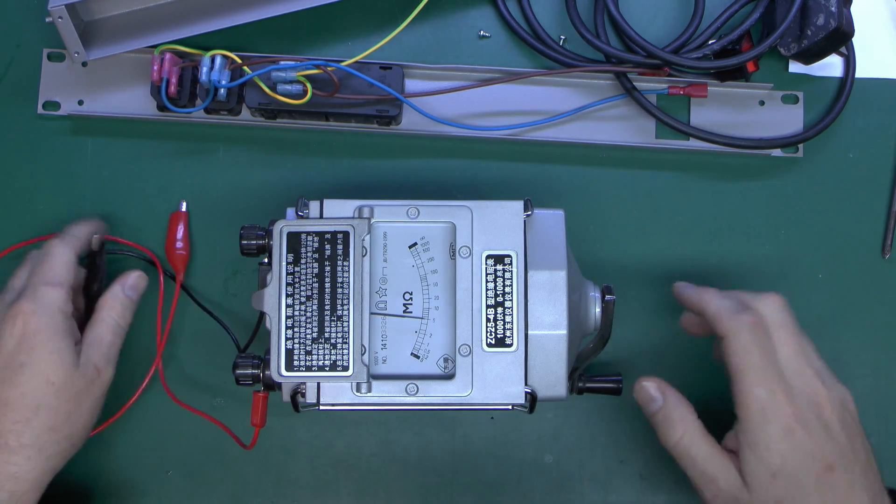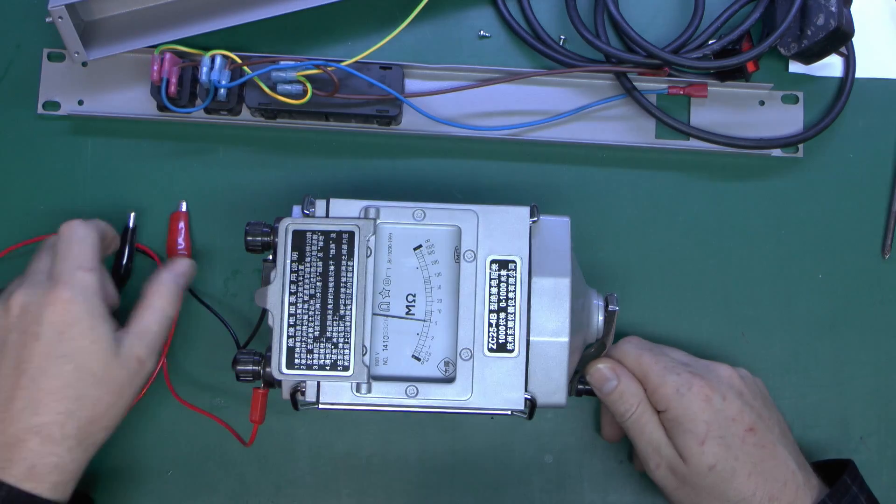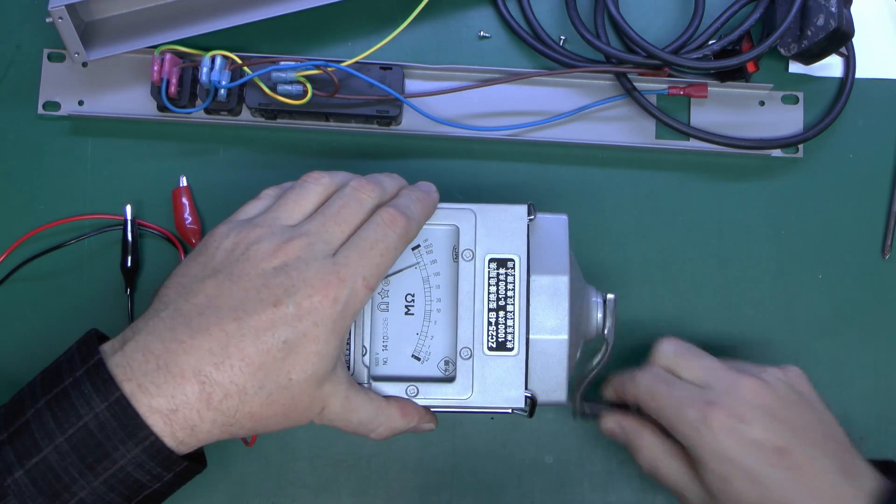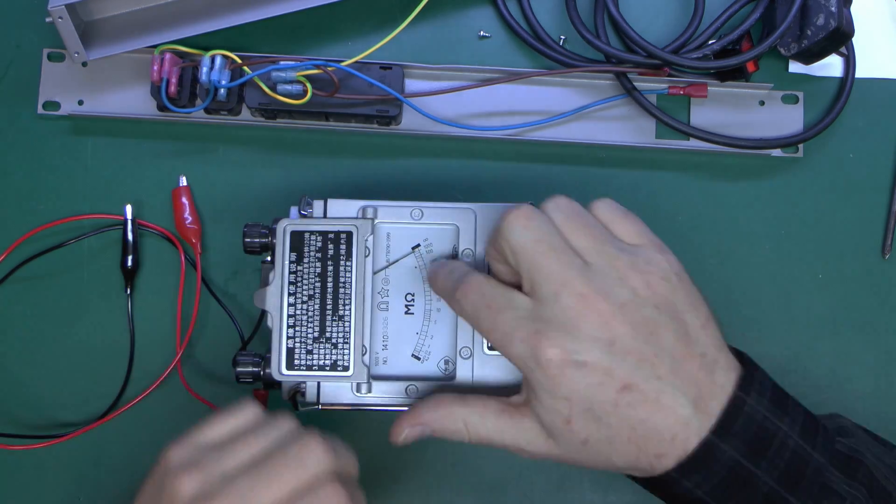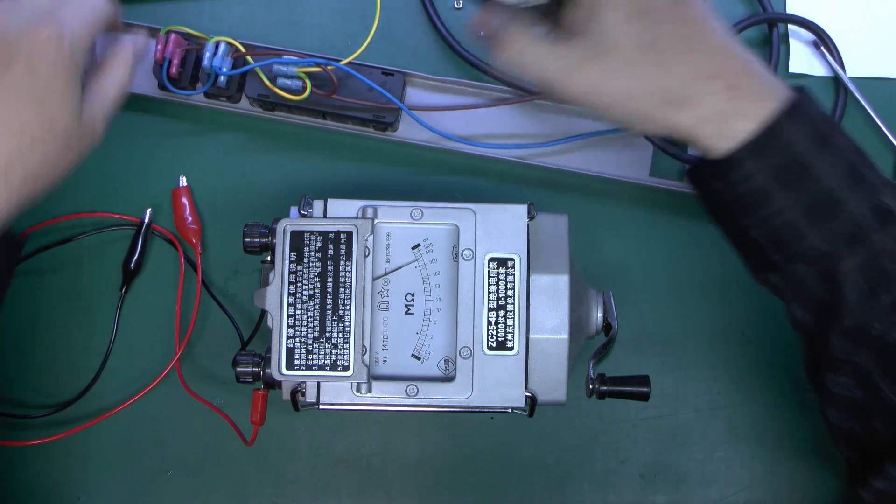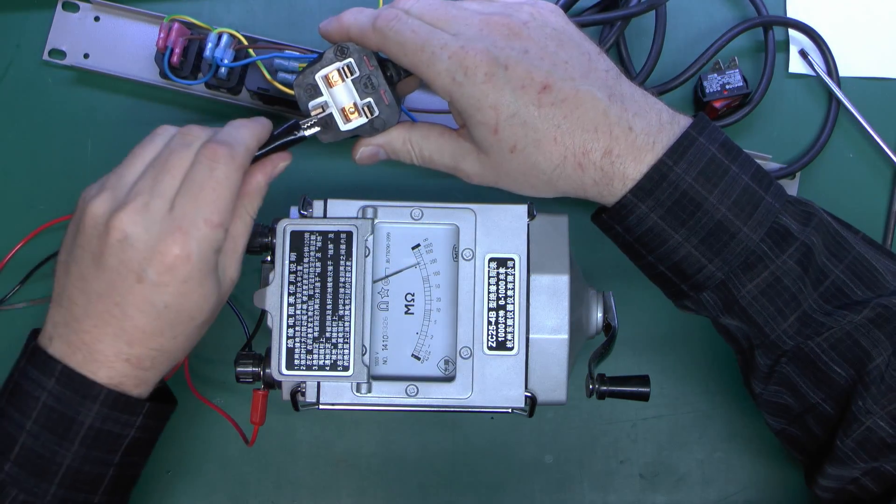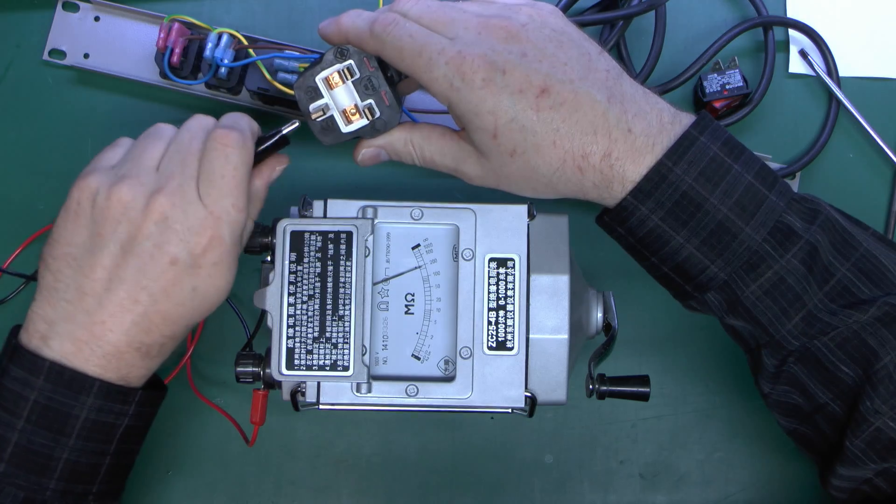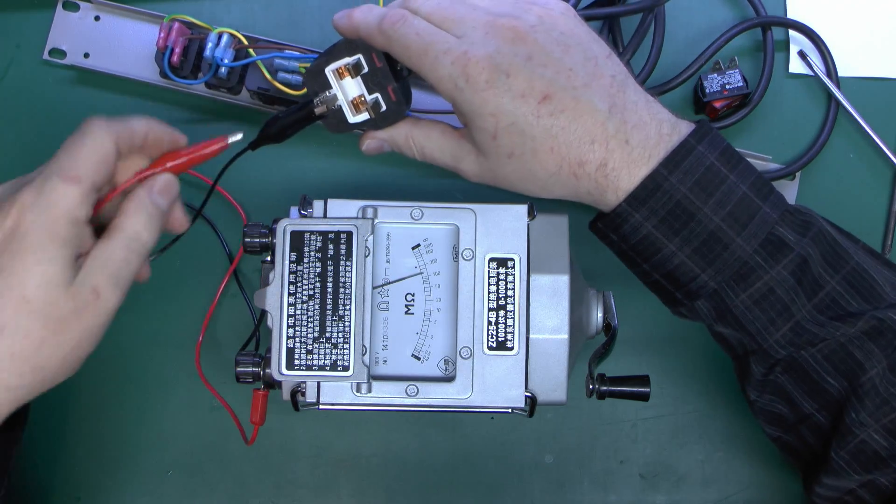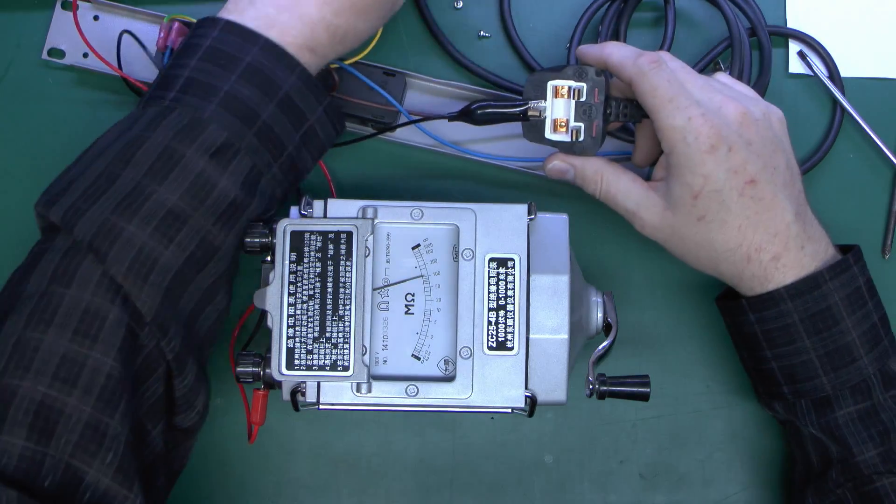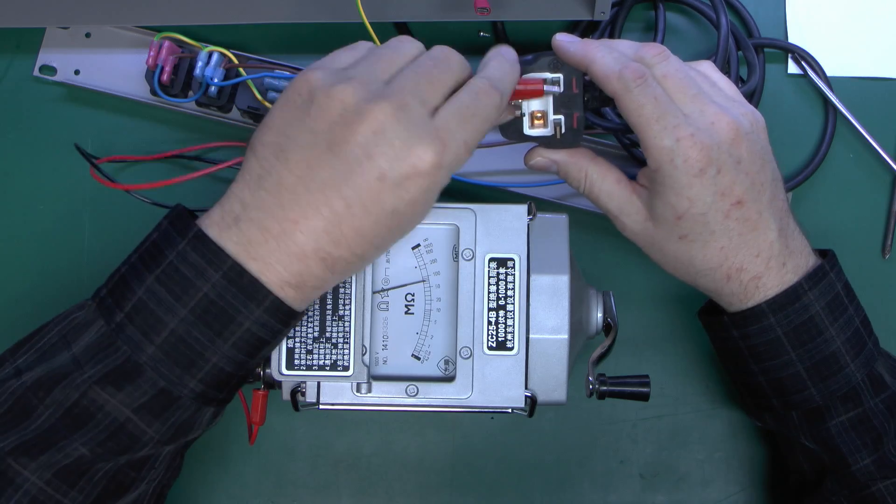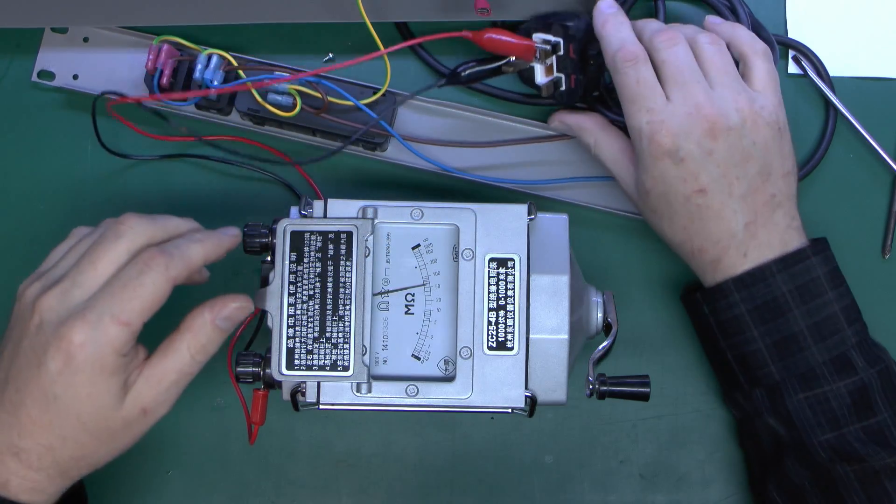So if we turn the handle with the thing just open at the end, and as expected, of course, it goes up to the infinity end there. So let's just connect it to this device here. We'll go between the earth and one of the pins to start with. And we're just testing the length of cord here, still got it disconnected at the end there. So we'll go between that and the neutral to start with and then we should crank the handle.